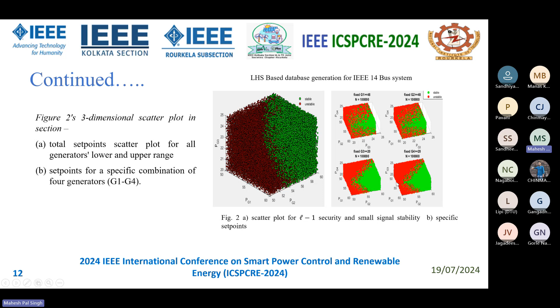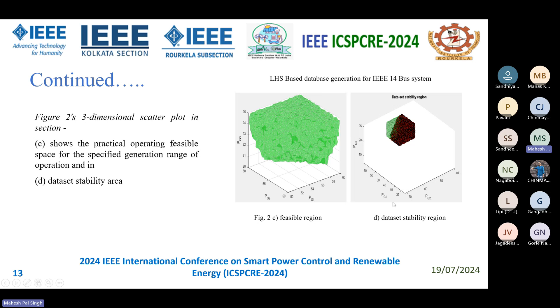These are the scatter plots of this data set, showing the generator combination for the security threshold, L-1 security, and small signal stability. These are specific combinations of set points for different generators, G1 to G4, since there are 5 generators — one is the slack bus generator and the other four change their combination. These are the feasible region identified for the system, and this is the stability region.